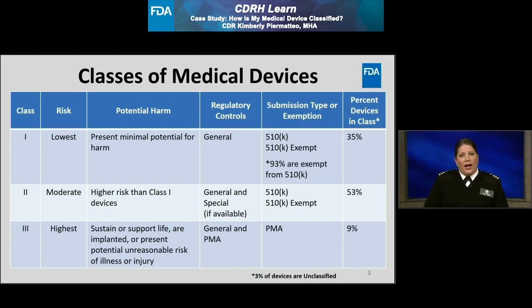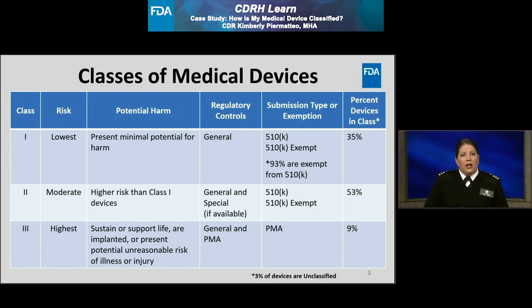Before I begin the case study, I'd like to review a few points made in the companion module. First, medical devices are classified based on risk. Medical devices may be classified as class 1, class 2, or class 3. Second, the risk of the device determines the extent of regulatory controls. And lastly, there may be an applicable premarket submission type for a device unless exempt. The table displayed on this slide provides an overview of the medical device classes and their applicable regulatory requirements.